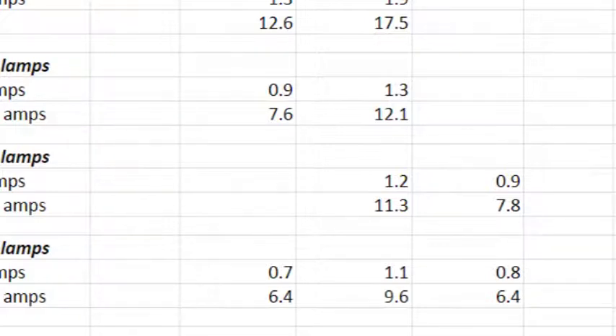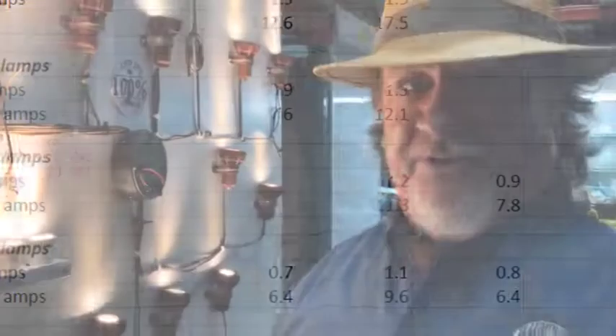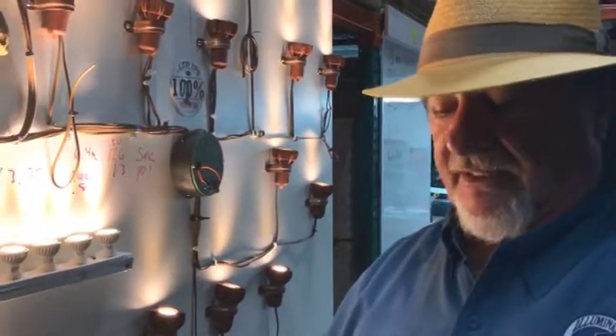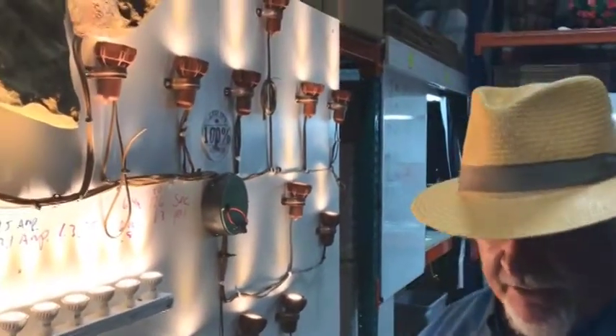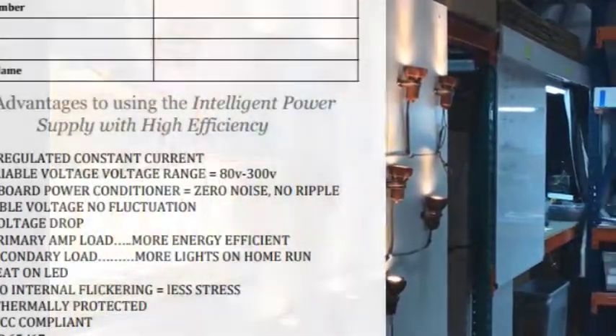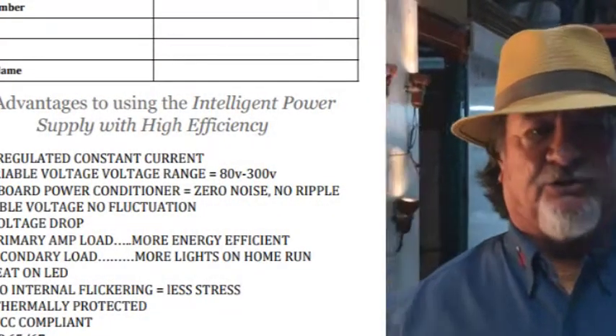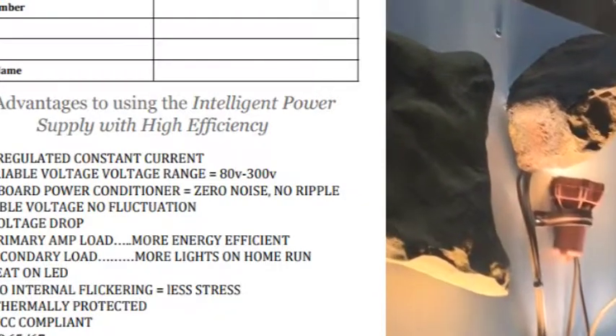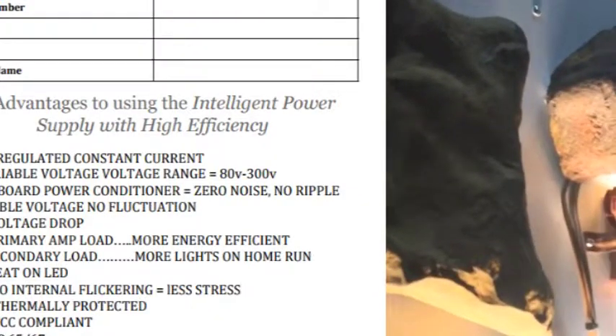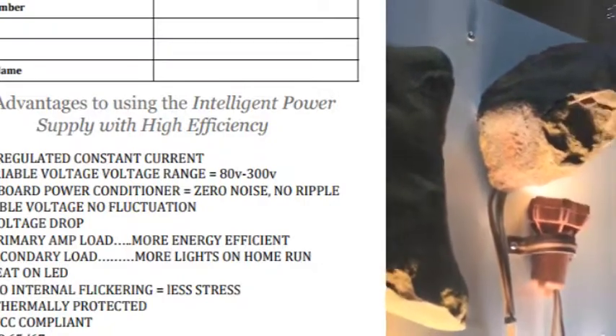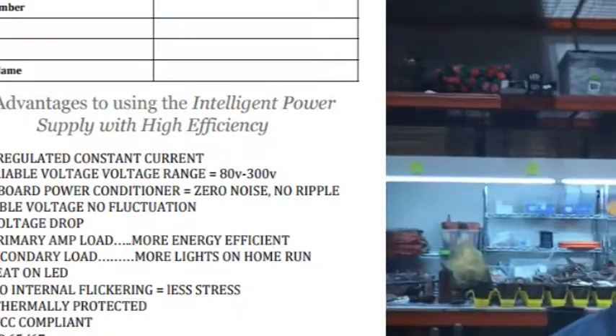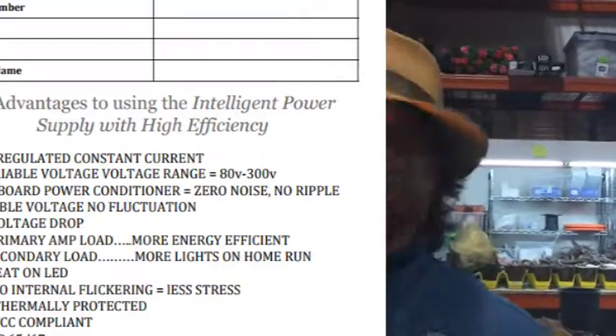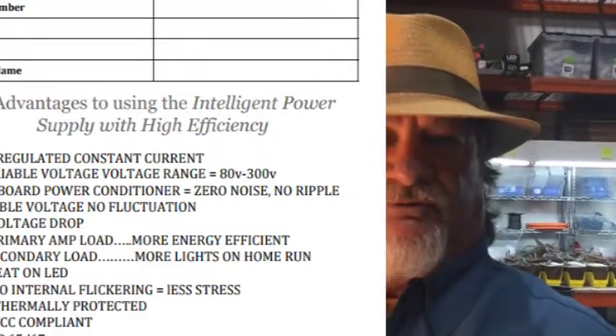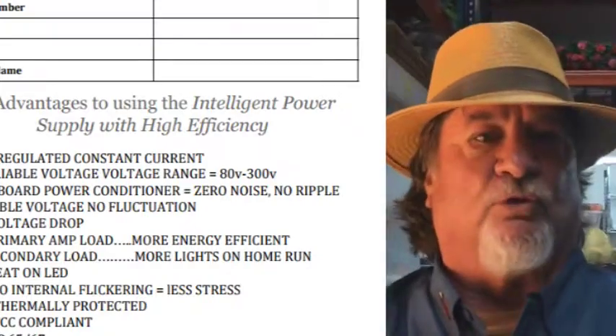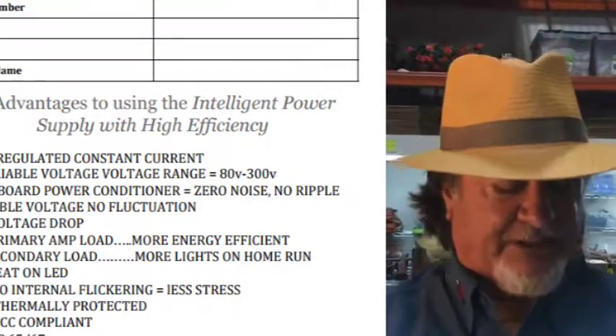It's mind-blowing. Now, some of the things, because I don't want to forget any, right? Here are the 16 things that are just mind-blowing about an intelligent power supply. It has regulated constant voltage. So if it's 13 volts out, it's 13 volts out unless you overload it. It'll always be 13 volts out. An AC magnetic transformer always drops a minimum of 1 volt at the transformer. That's how they work. These transformers, you're allowed to hook up between 80 and 300 volts. 277, 240, 208. Commercial jobs, electricians.